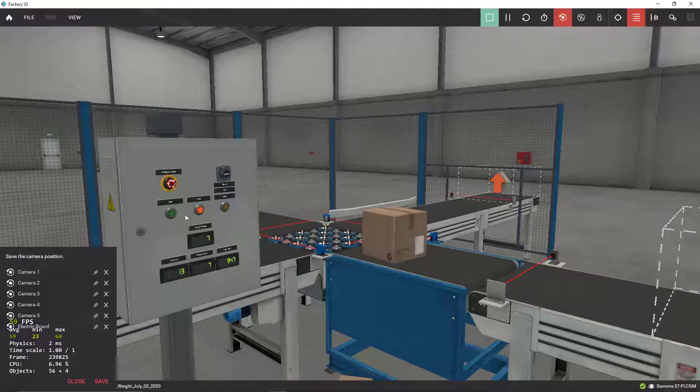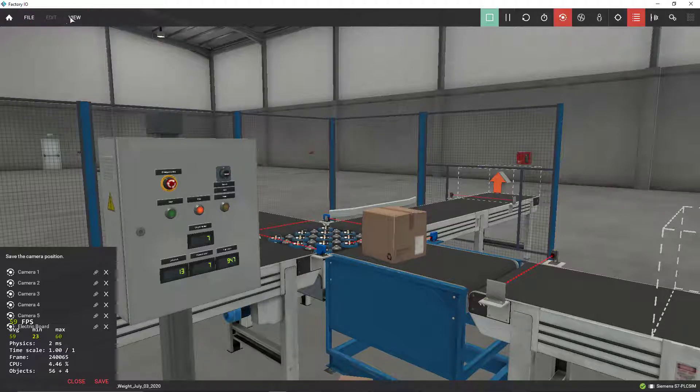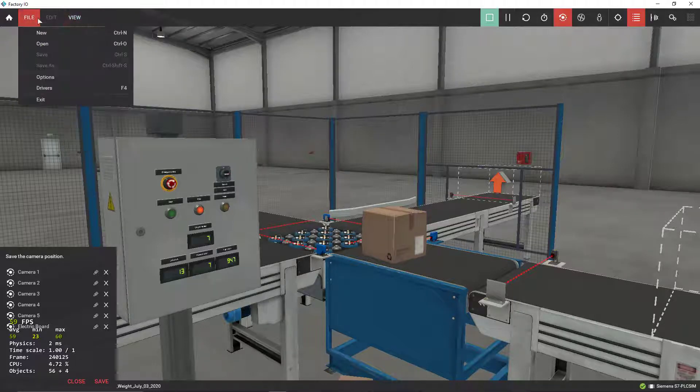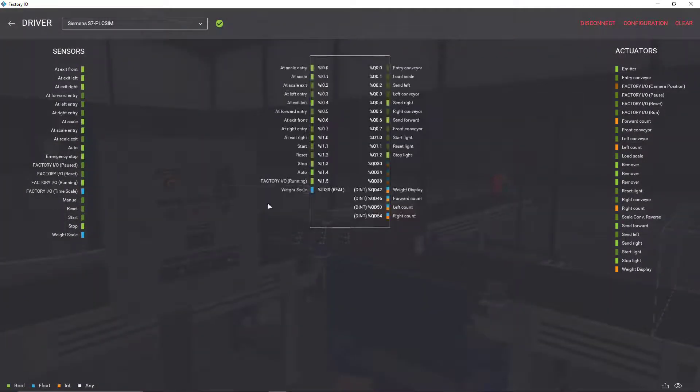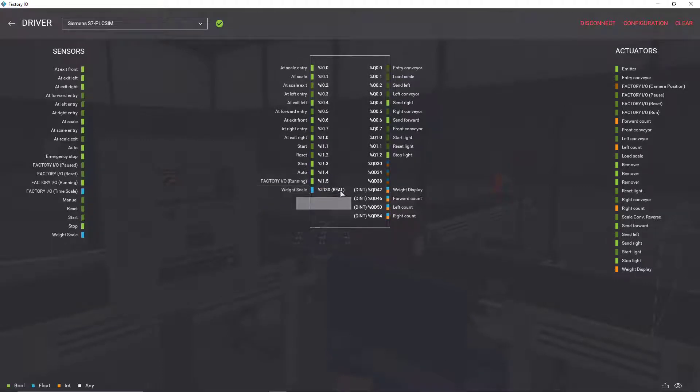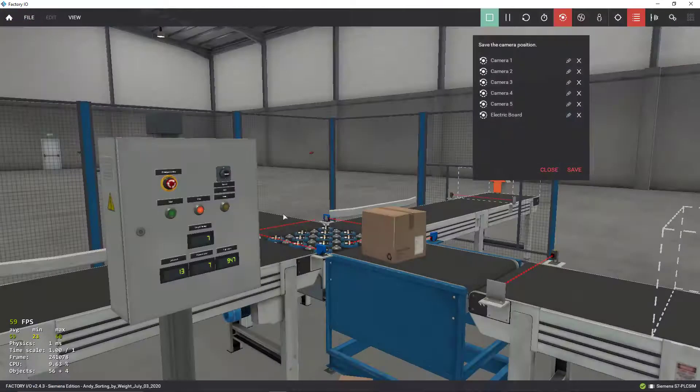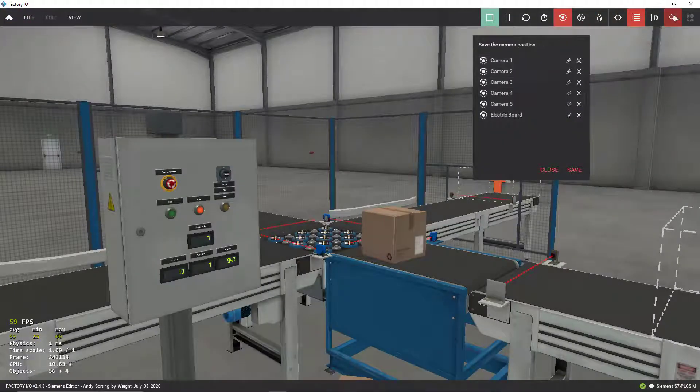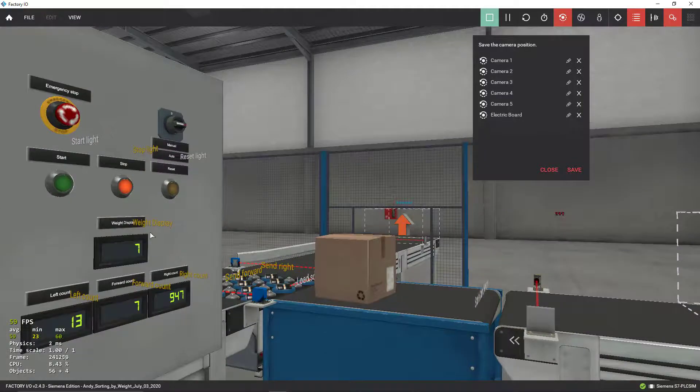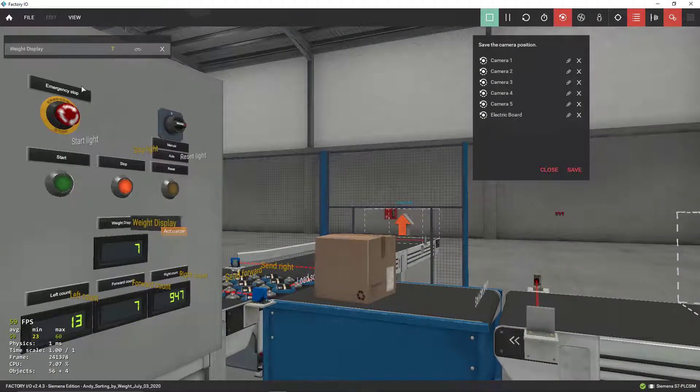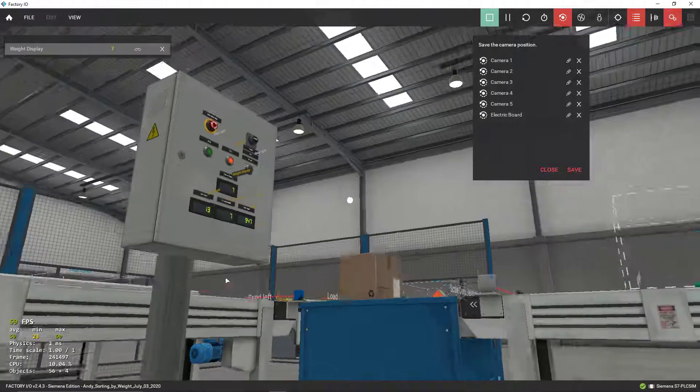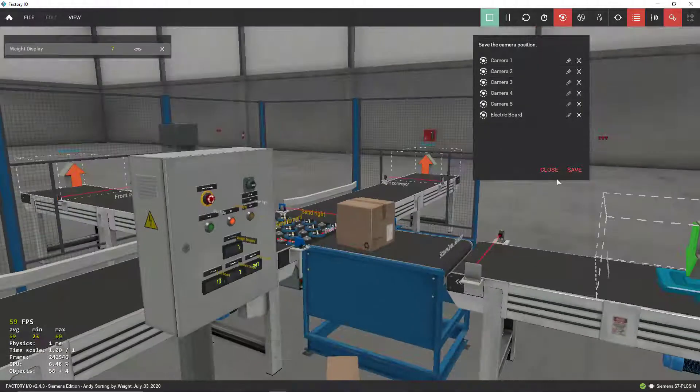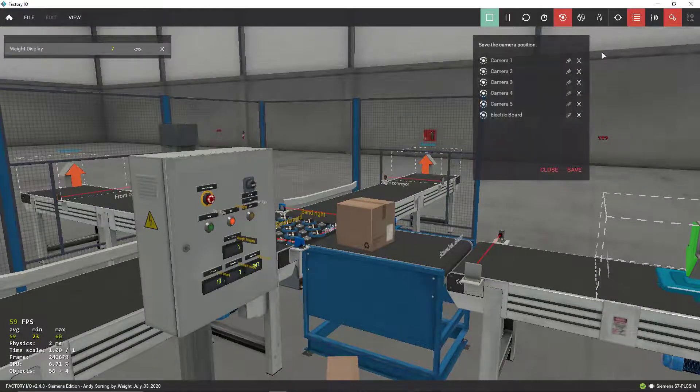So I'm converting from real to a double integer and put it on my weight display. This tag, my weight display, this is where it's coming from. If you see my drivers, my weight scale is coming from here as an input as a real one, and then I'm converting it to a double integer right here and put it in tag display weight display. That's this one over here, weight display. You see, right over here.